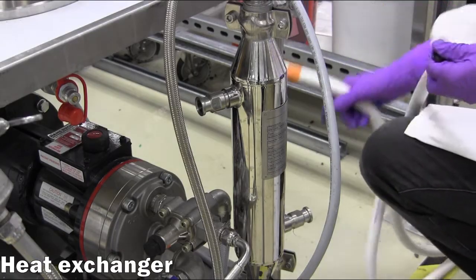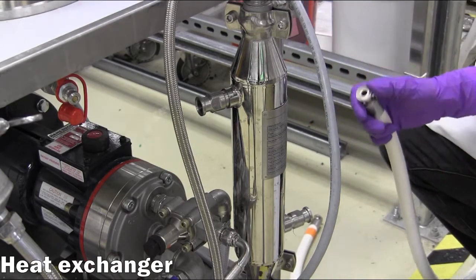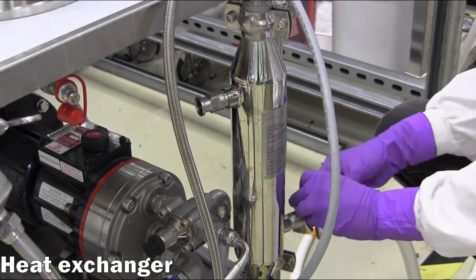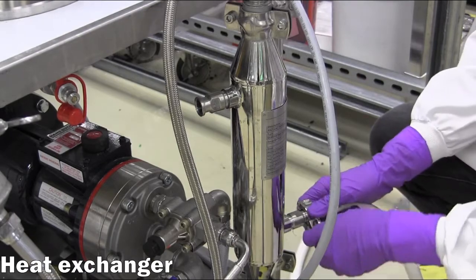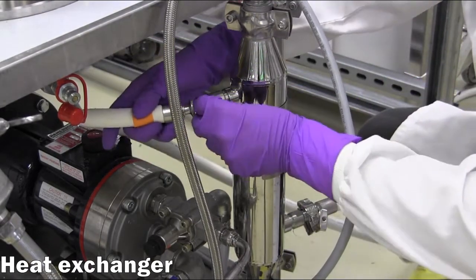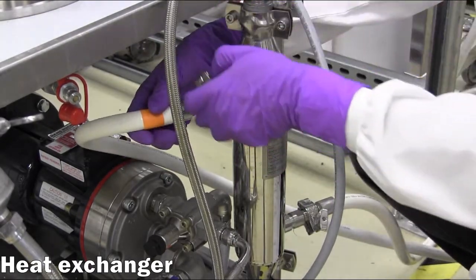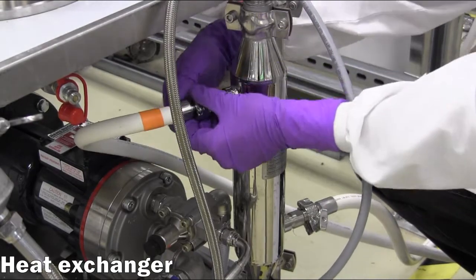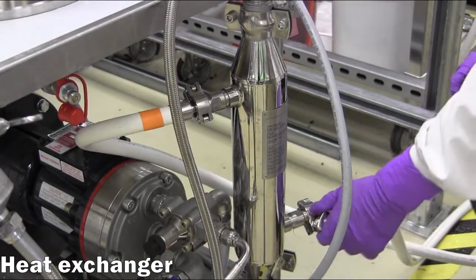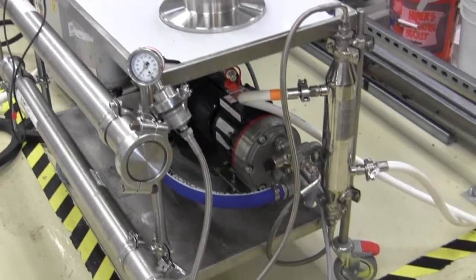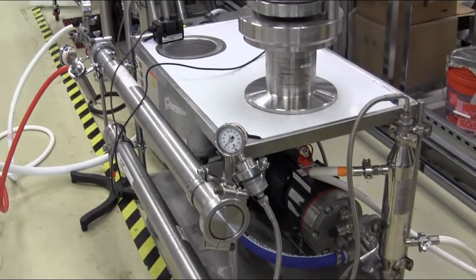Lastly, make the hose connections to provide chilled water to the heat exchanger, where the supply line is connected to the bottom side port, and the return line is connected to the top side port. The unit is now fully assembled.